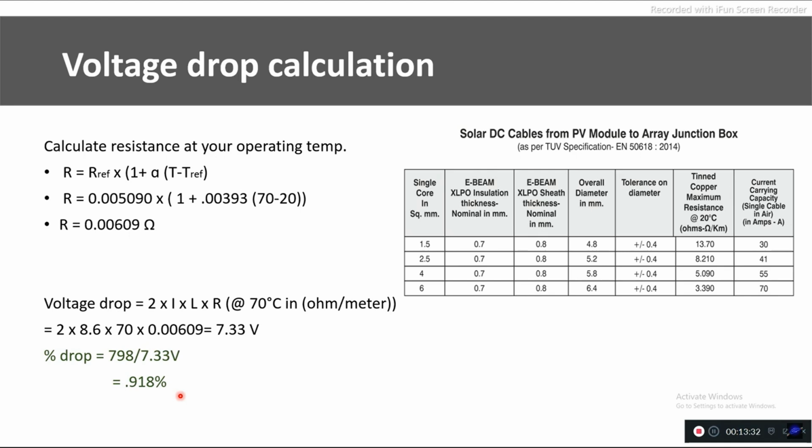So guys, I would still like to tell you some practical tips. The first thing is that whenever the cable distance goes above 50 or 55 meters, then go for a 6 square mm cable.